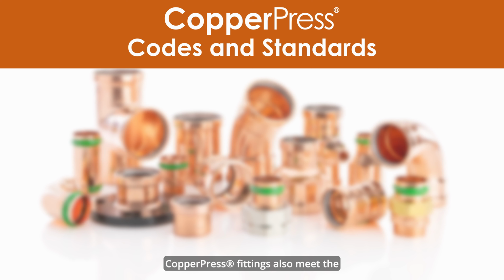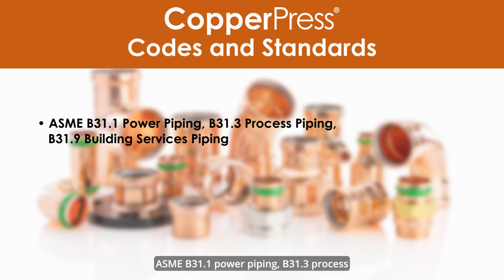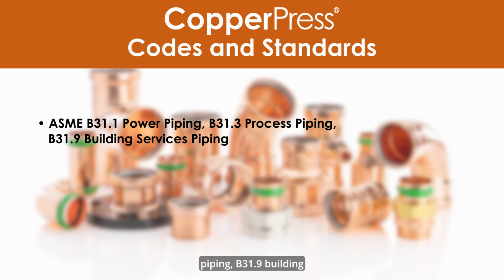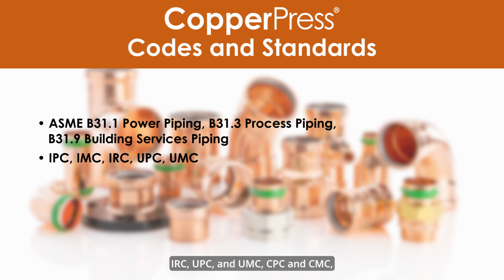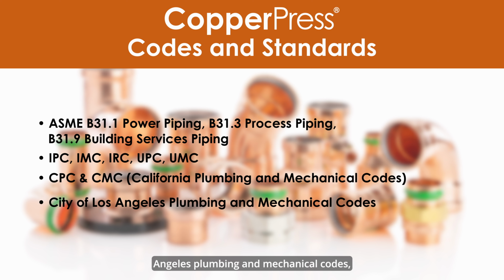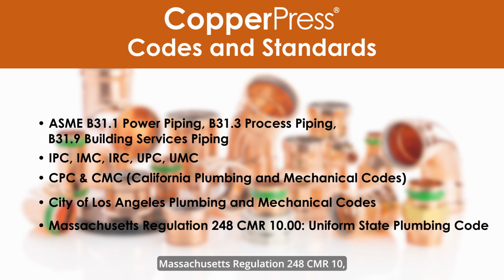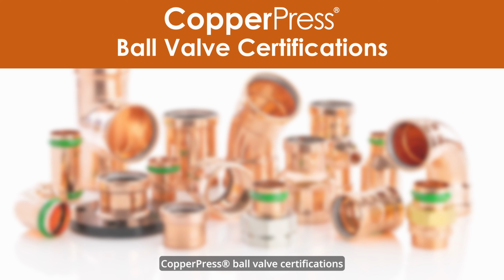Copper press fittings also meet the following codes and standards: ASME B31.1 power piping, B31.3 process piping, B31.9 building services piping, IPC, IMC, IRC, UPC, and UMC, CPC and CMC, California Plumbing and Mechanical Codes, City of Los Angeles Plumbing and Mechanical Codes, Massachusetts Regulation 248 CMR 10, Uniform State Plumbing Code, Massachusetts State Building Code 780 CMR, 9th edition, Chapter 28.